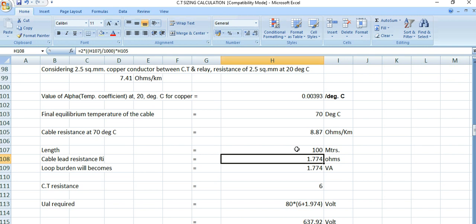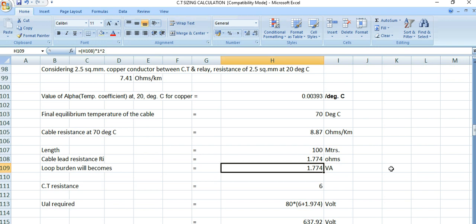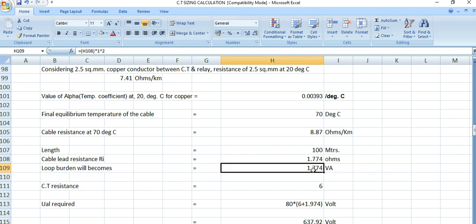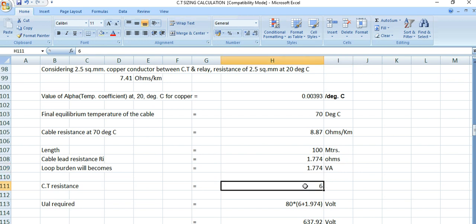The cable lead resistance is twice (for go and return): twice into 8.87 ohms/km over 100 meters gives 1.774 ohms. So the loop burden is 1.774 VA — since the CT secondary is 1 ampere, ohms and VA are the same here.